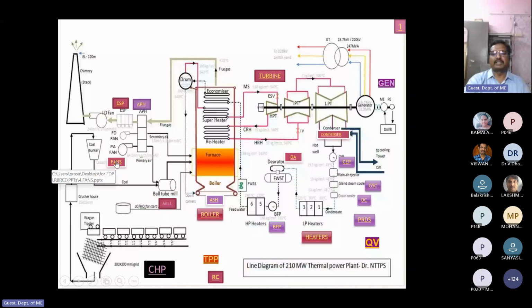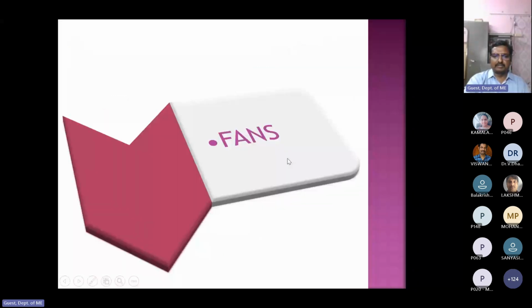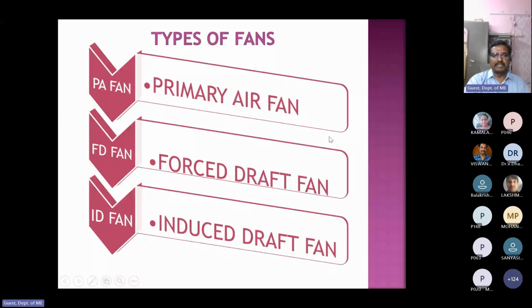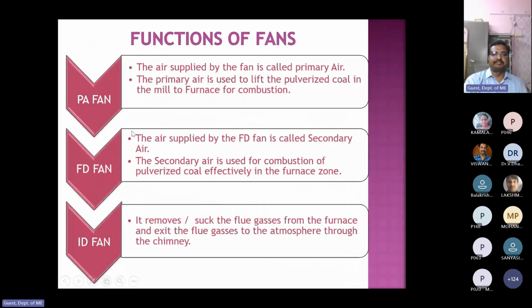So this coal powder goes to the furnace with the help of primary air, which is produced by a fan. There are several fans in the boiler. They are called primary air fan, PA fan, FD fan, and ID fan. The PA fan's purpose is to carry the fine fuel powder to the furnace directly. The FD fan is called the forced draft fan. Its purpose is to supply air to the furnace directly for complete combustion. Here is another fan, the induced draft fan, because it is a balanced draft boiler. The induced draft fan is used for evacuating the flue gases from the furnace. It is installed before the chimney. These are all the PA fan, FD fan, and ID fan.